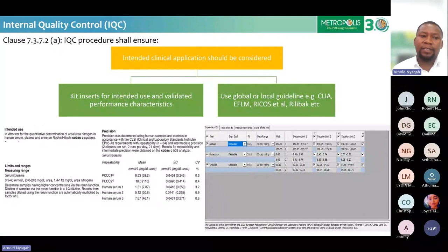Allowable errors that are there, all these standards can be used, okay. Then on the same IQC procedure, you should be able to ensure that it allows the detection of either lot to lot or calibrator variation or both, okay?